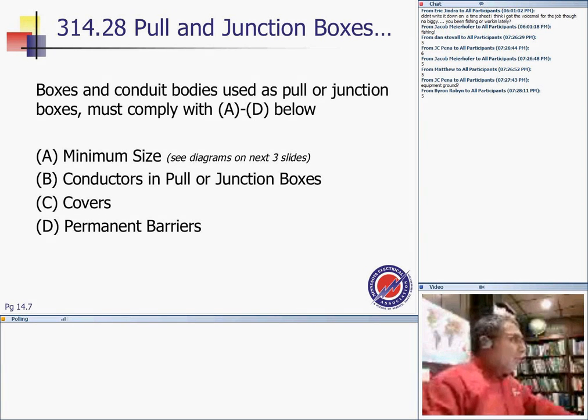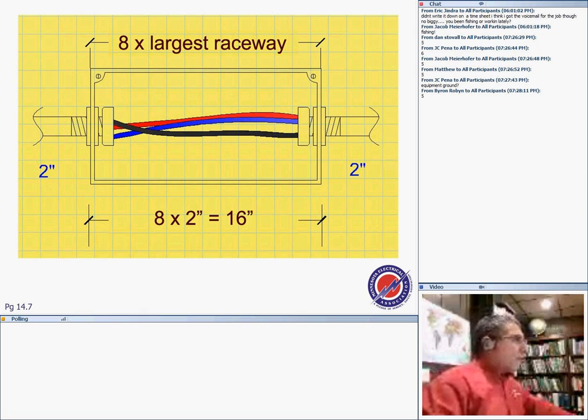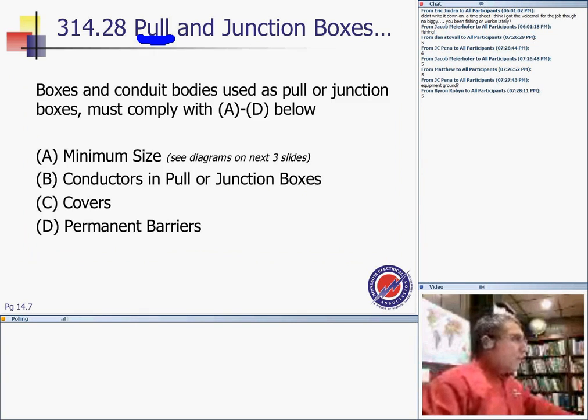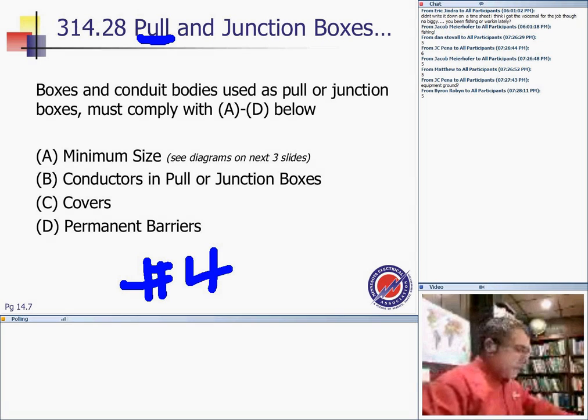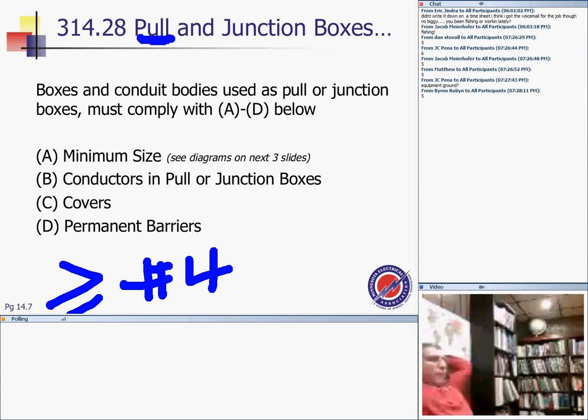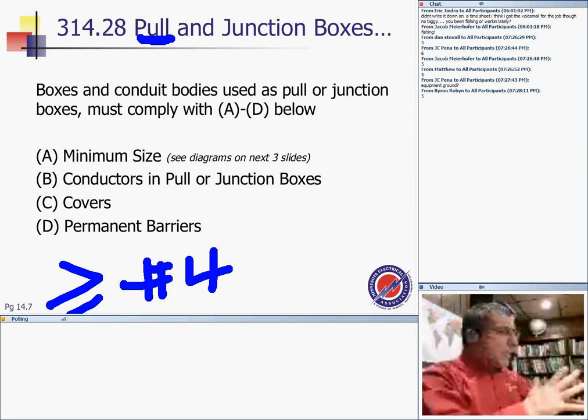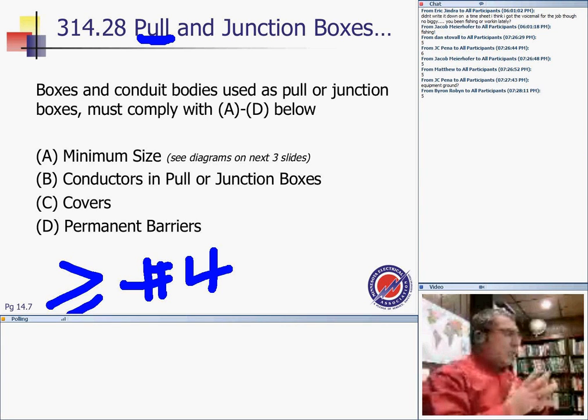We talked, guys, about the pull boxes, especially pull boxes. For a box to qualify as a pull box, here's the rule. It has a number 4 conductor. So for any box to qualify as a pull box, it has to have at least one conductor that's equal to or larger than number 4. So if I have a conductor that's number 4 or larger, then my box qualifies as a pull box, and the calculation for J boxes no longer applies to it. So a J box could be used as a pull box or a J box.